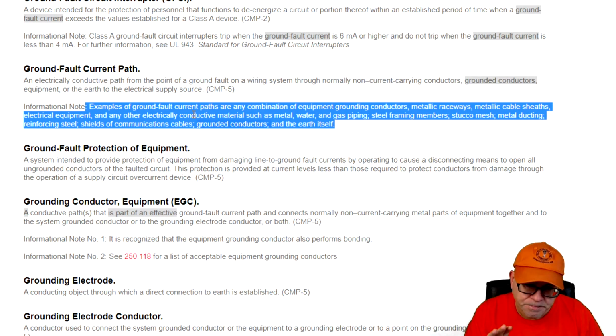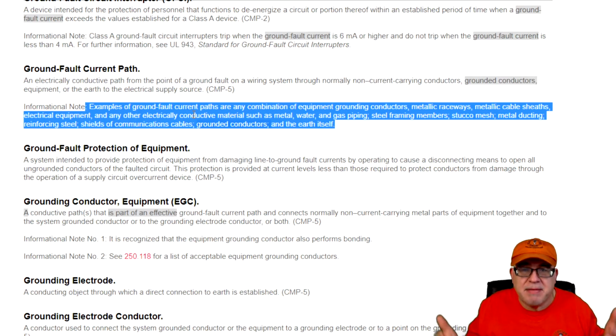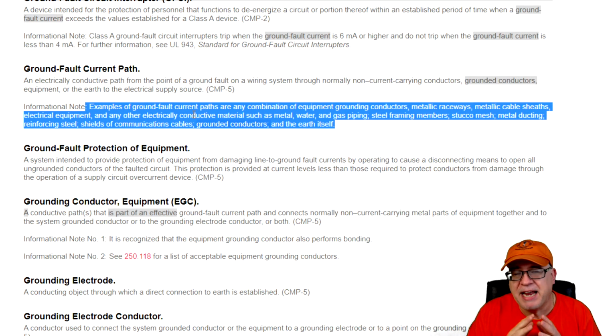Now, remember, again, when we're talking about establishing things like a low impedance ground fault current path, it is slightly different, because a ground fault current path, as you can see, can be many things, okay? But a low impedance ground fault current path that's dictated by Article 250 for the operation of an overcurrent protective device, it is important that we have a low impedance.